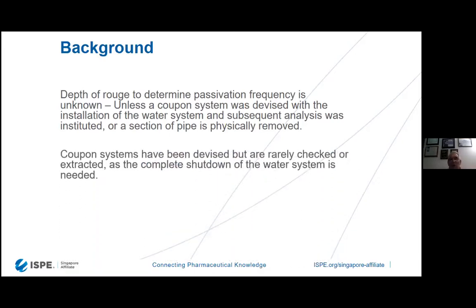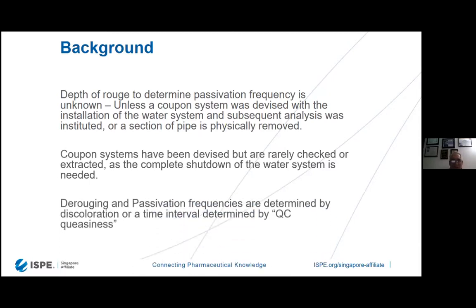And we decided to go to this kind of system, which I call QC queasiness. Lots of times, derouging passivation is determined by discoloration, or a time interval that someone decided by QC. So how did this happen? Typically QC would say, well, we're going to do derouging passivation once a year. And as a scientist, I would say, how did you arrive at that? They said, well, we do everything else at once a year. It was not based upon scientific data. It was based upon what QC could tolerate before they couldn't tolerate it anymore.